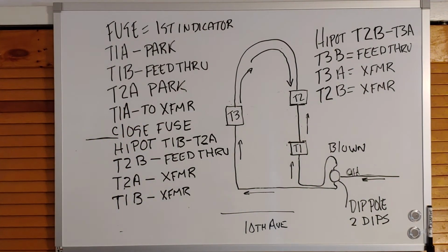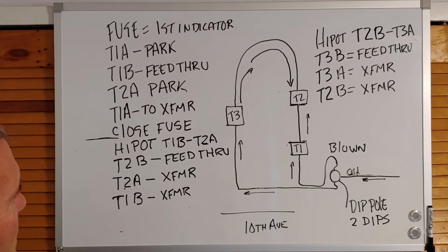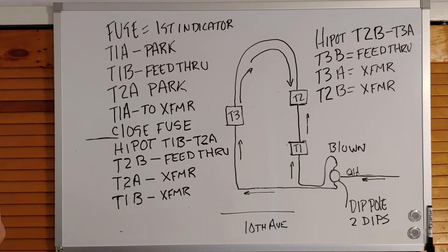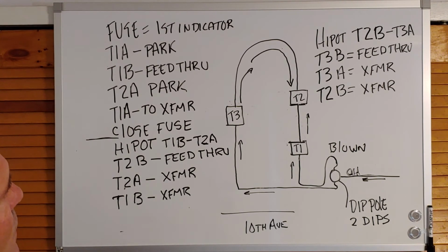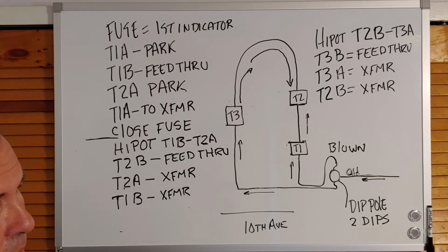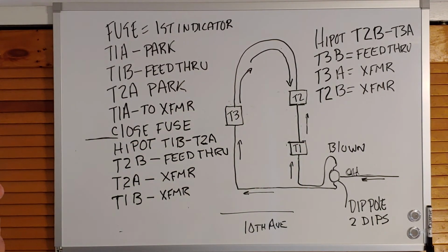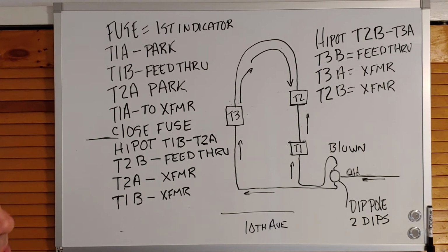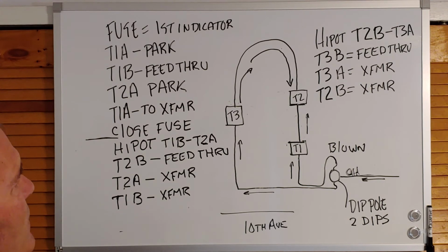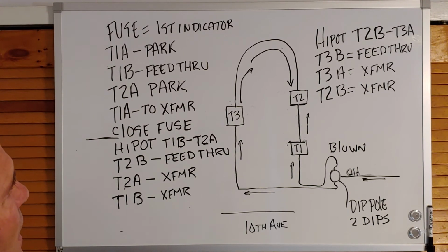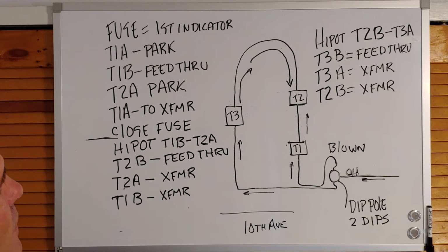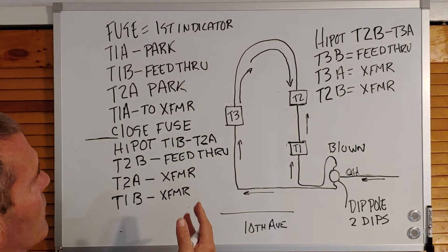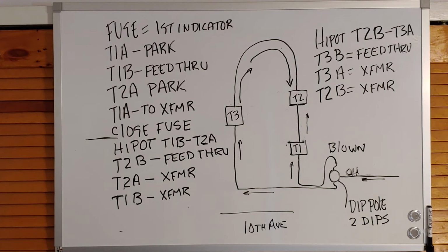All right, so now you've had two methods: one is the fault indicator way of how to isolate, and two is the high potting method with no fault indicators. Once you've identified it, we're going to go back on that and I'll take all of this out, but do write it down, because these are the processes and you'll be quizzed. I'm going to give you a quiz that says I have no fault indicators and I've high potted, and ask you to high pot and re-energize as you go. That's what we're doing here, from T1 to T2 to T3. You're looking at it. Obviously you've got it right here, but I want you to know the steps as far as that's concerned.